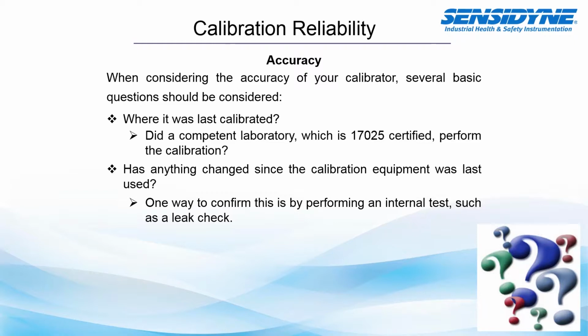Sometimes as we take calibration equipment out to the field, we take it back, it gets moved from one location to another. Damage could occur to your calibrator. Can my calibrator be checked in the field to ensure that it is still performing as expected? One way to confirm this is by performing an internal leak test if such a leak check is possible with your calibration device.